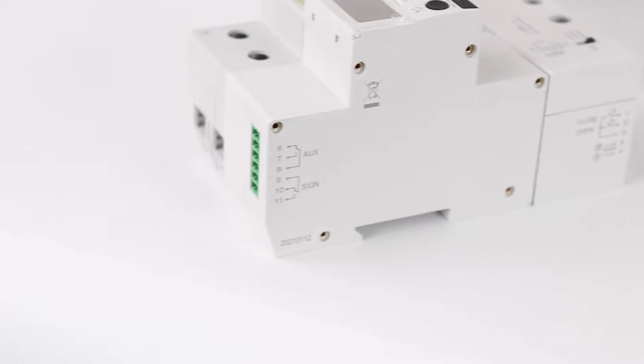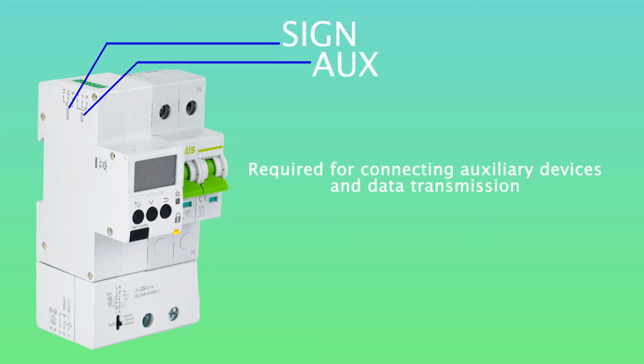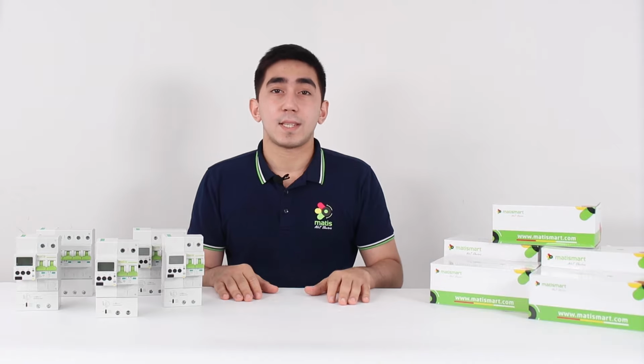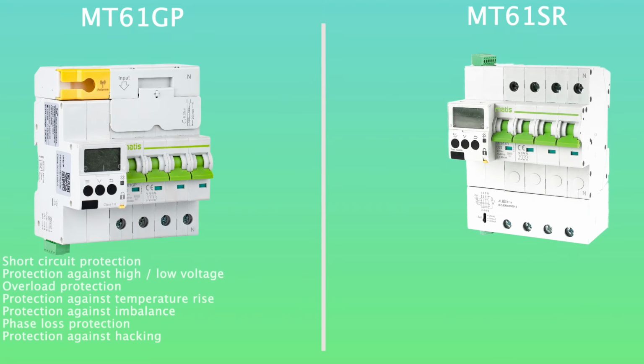But about everything in order. There are terminals on the top and the bottom of the device, and the purpose of the particular contact is marked on the side. The terminals on top, on which the initials AUX and SIGN are indicated, are intended for auxiliary devices and for transmitting information about the state of the power grid and the device. In the case of MT61GP, this device has a wider protection functionality.